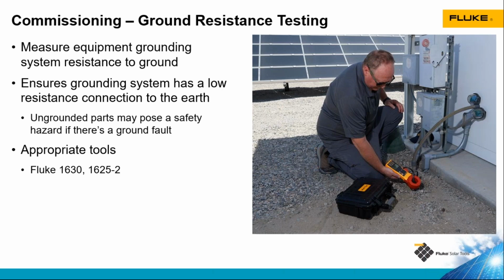We have two tools here. The 1630, I believe, is the one pictured here. This is a stakeless test. It induces a current signal onto that conductor, sends the current through the ground through an auxiliary ground rod, and then back through the equipment grounding conductor, and measures the current there to determine how the resistance to ground is. There's also the 1625-2, which has multiple stakes if you don't have an auxiliary path to ground, so that can do a couple different types of tests as well.